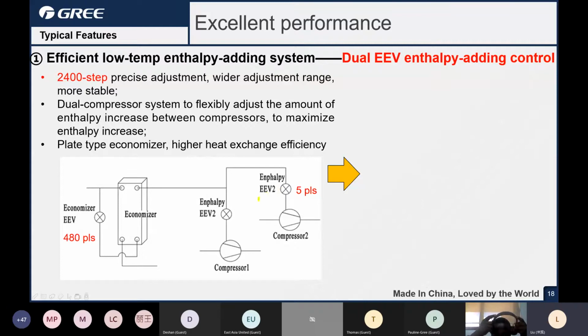So depending on the node and control of the main board, the unit will adjust the opening of the main expansion valve or the enthalpy expansion valve. That means we can get 2,400 step precise adjustment because of these two expansion valves.